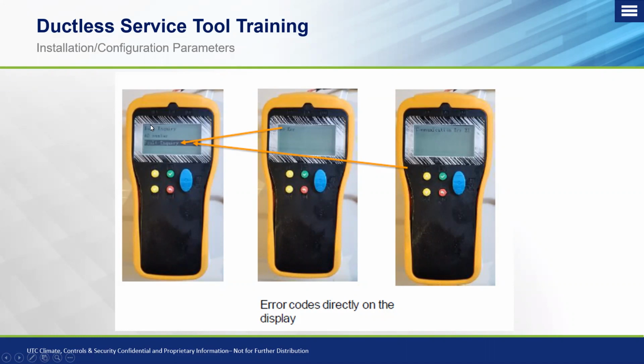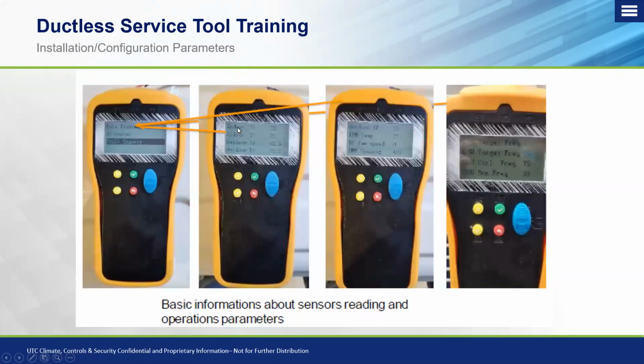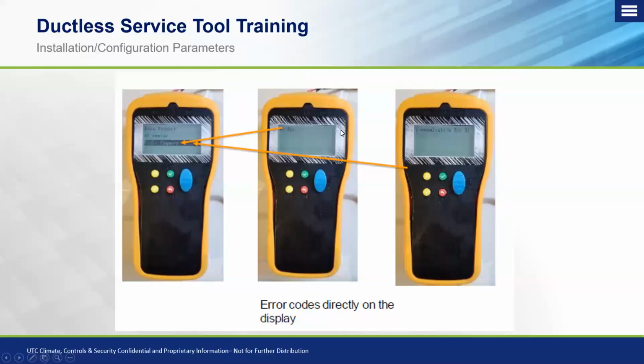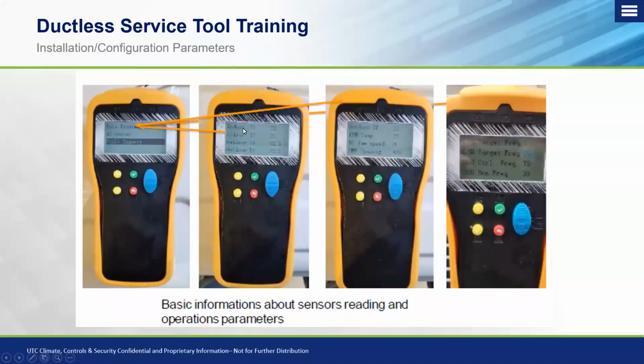So once you want to get into this menu, you go ahead and hit your green check mark again, and you'll enter into the data inquiry. From there, you can get information such as your T1, T2, and T3 sensors. Now you can see on here, they're all displayed in degrees Celsius. Okay, so if you're only hooked up to the outdoor unit, you're not going to read a T1 and a T2 temperature reading. You're only going to read the sensors of the outdoor unit, which is their T3, T4, and T5 temperature sensors.